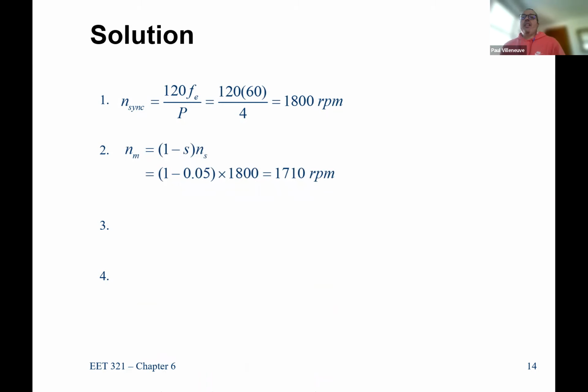The actual speed of operation, so the mechanical speed, is 1 minus the slip times the synchronous speed. So this machine puts out 10 horsepower, which is its nominal rating, at 1,710 RPM. Our electrical frequency on the rotor, we find by taking our slip, which is 5%, multiplying it by our electrical frequency, 60 hertz, multiply those 2 together, and the actual frequency on the rotor, that's the electrical frequency, is 3 hertz. And then our last part, which is the output torque.